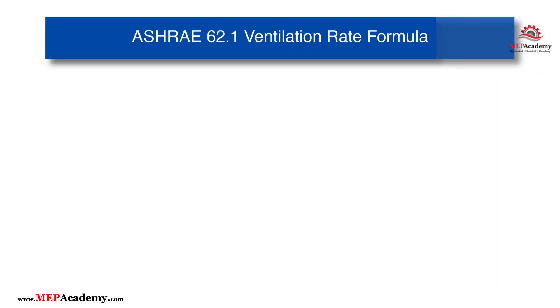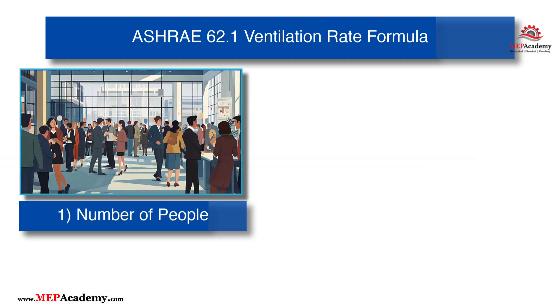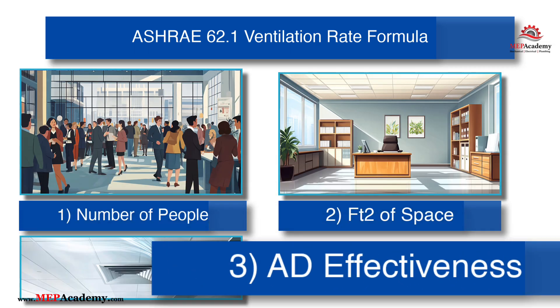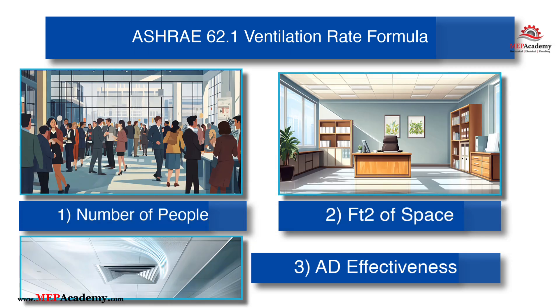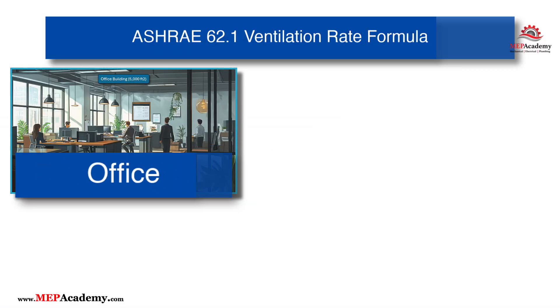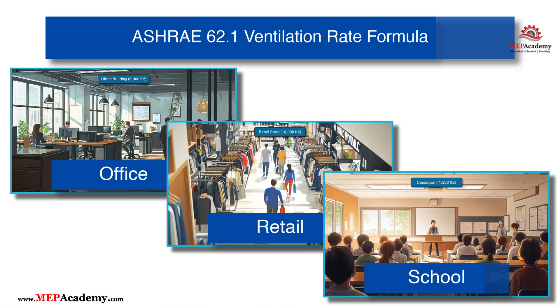The ASHRAE 62.1 Ventilation Rate Formula is based on three key factors: the number of people in the space, the square footage of the area, and the zone air distribution effectiveness. The number of people determines the amount of fresh air needed for occupants, while the square footage accounts for the ventilation required to offset contaminants from building materials and activities. The zone air distribution effectiveness adjusts the airflow based on how well the ventilation system distributes air within the space, ensuring optimal air quality. Let's go through three examples — an office, retail store, and classroom — to illustrate how the ASHRAE 62.1 Ventilation Rate Calculation works in different spaces.